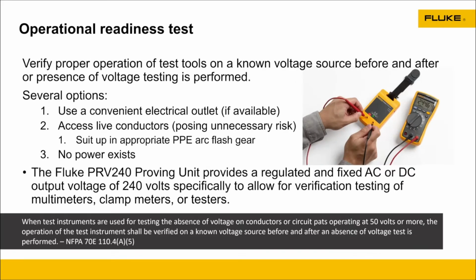But what happens if you don't have a known voltage source? There's actually a lot of times where you're out in your truck, you're out in the field, maybe you're on a construction site, you're still running and doing some stuff. Maybe there's a voltage drop out there for you. There's not a good way to get a known voltage source on that. That's where you can use a proving unit, like the Fluke PRV240. It actually generates 240 volts at almost 0 current and allows you to do a dead live test on your meter and validate that it's working correctly. So again, learning the safety procedures, learning how to mitigate some of those safeties that could potentially cause that arc fault, that problem. This is a great way to do that.